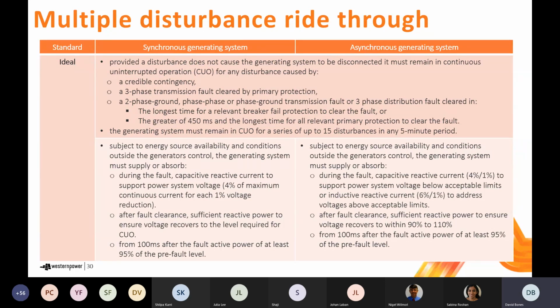So just stepping through that in a little bit more detail, for the ideal standard, as you can see, there's a series of, if you like, eligible faults. So credible contingency, three-phase transmission fault cleared in primary protection, two-phase to ground, phase to ground, phase to phase transmission faults, or three-phase distribution faults cleared in the longest time for the relevant breaker fail protection, or the greater of 450 milliseconds and the longest time for all relevant primary protection to clear the fault. And so the requirement is then for any combination of 15 of those disturbances occurring within a 5-minute period.